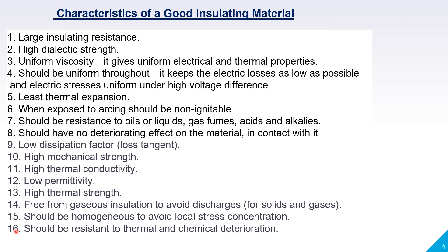They should be free from gaseous inclusions to avoid discharges and should be homogeneous to avoid local stress concentration. They should be resistant to thermal and chemical deterioration. In electrical devices there will be mechanical, thermal, electrical, chemical, and environmental changes, which may increase stress and aging.